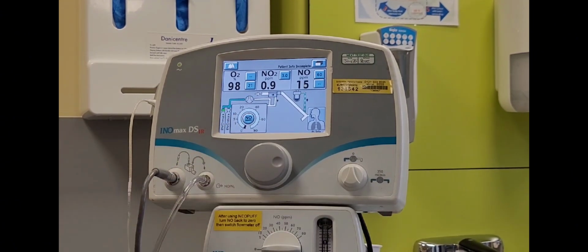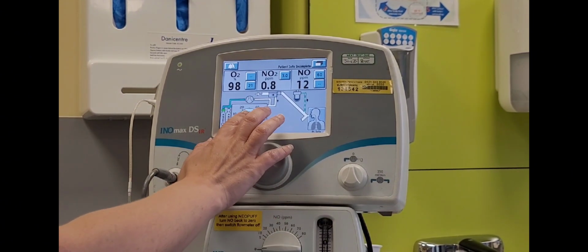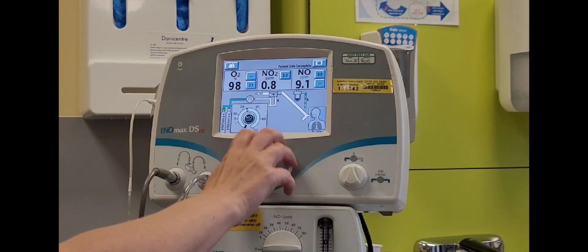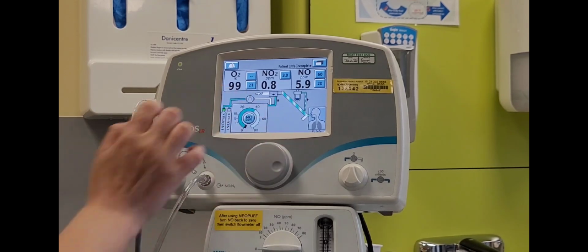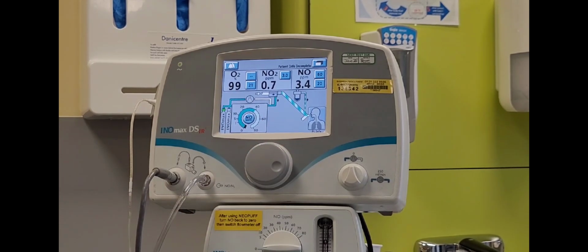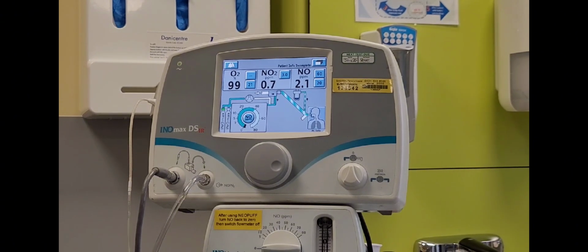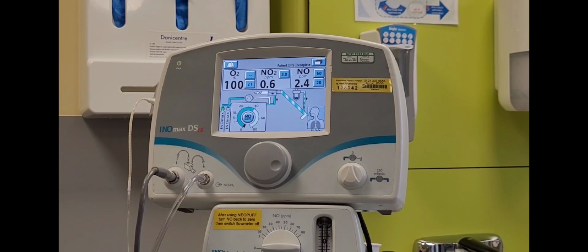The performance test requires the oxygen to still be on. Set the dose to 40 and check that the FiO2 is 95. The NO2 is equal to or less than 1.5 parts per million and the NO is between 35 to 45 parts per million. This can take a few minutes. Once achieved, turn the dose back to 0.